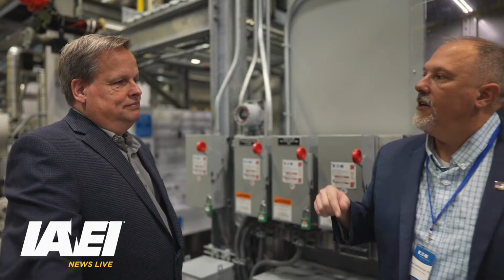And obviously we don't have to agree either. So in any case, it's a valid concern. So we put a requirement in the code that said if the battery expires, for the lack of a better word, then the lights should automatically turn on. And I think the TIA corrected that, I think rightfully so. The TIA said that's a safety concern, but here's the thing.